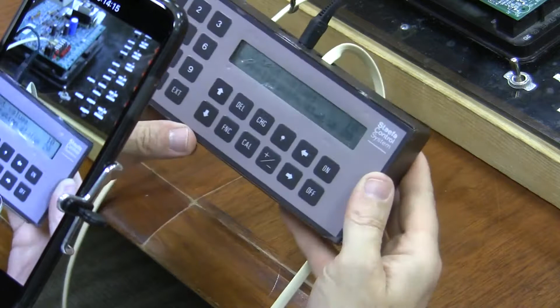Now I'm going to scroll down and look at what else he'll tell me. He'll tell me whether he thinks he's occupied or unoccupied. He'll tell me whether he thinks he's in warm-up mode. He'll tell me how much override time is left. These thermostats have a little button on them that you can put the controller in override mode by pushing that little button, and what that does is makes the card go occupied for a set specified amount of time.